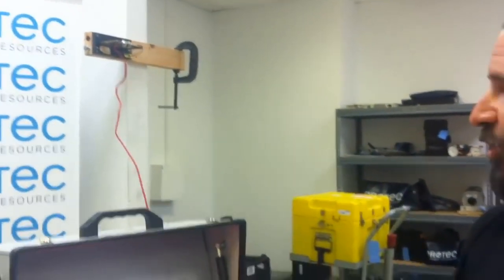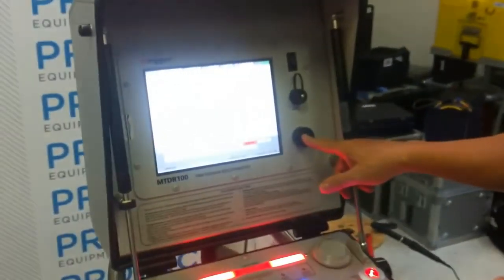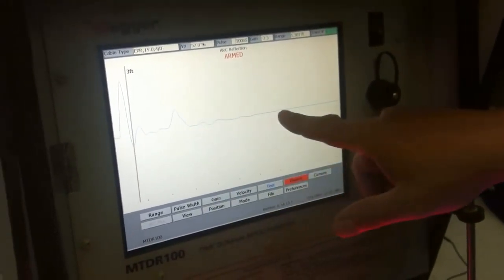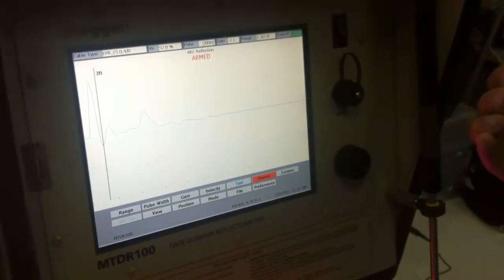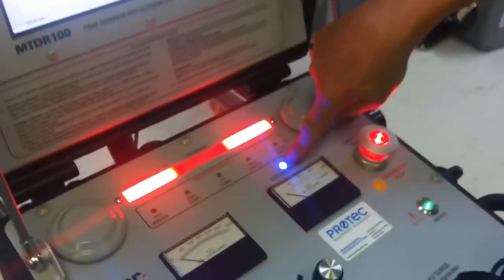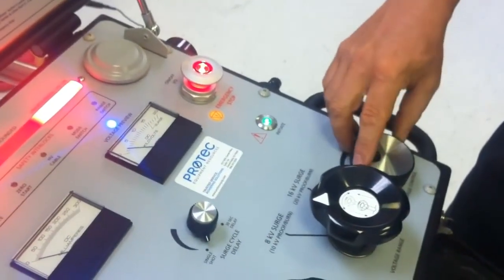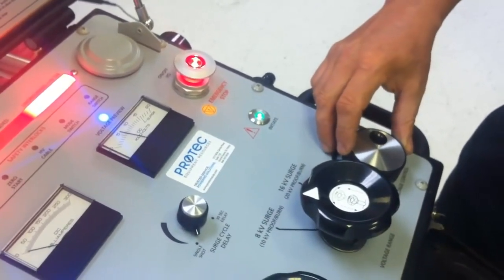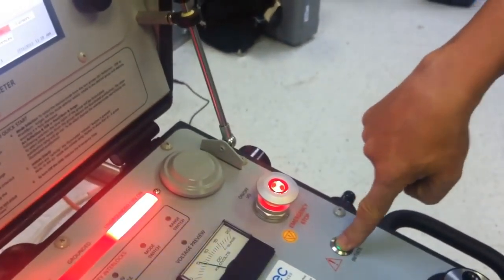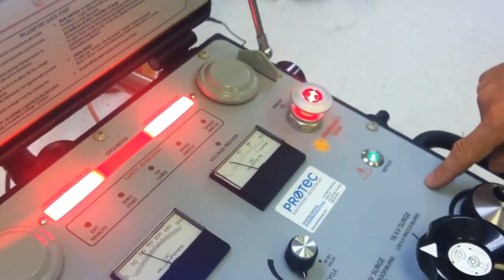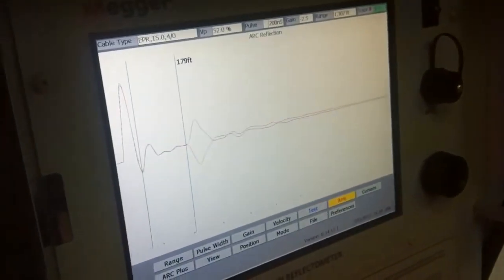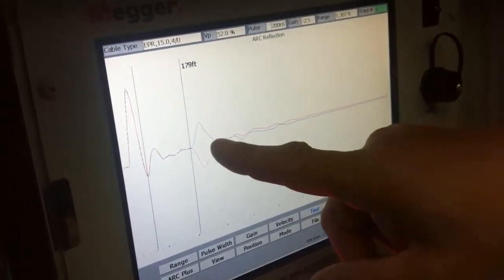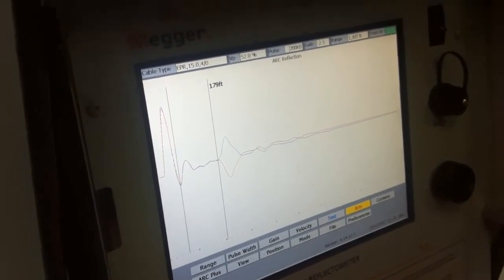During the high voltage test, what I want to do is capture the arc that is created through the discharging of the energy through my test gap. So arming the system, basically then, the instrument will go to arm, my low voltage image will be frozen to display memory, and the instrument is waiting for a trigger event before it starts to update the patterns. You'll notice that I'm in a voltage preview mode. I'm going to elevate my output voltage to the same 6 kV that I used before. And when I'm ready to run the test and to capture the event, I merely come to the initiate key, depress it. My radar will charge, discharge, and the red waveform indicates my high voltage pattern. The negative reflection shown is the short circuit that is caused during the arc.